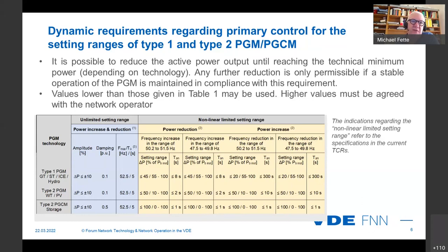Everything is tested in the factory. Everything is tested under the conditions we have to establish at the moment. But we want to know how it works in the future, and whether it works when we lose short circuit ratio, when the grid becomes weaker than today, and we lose inertia, so that the different plants will be operated and support the grid, supporting and forming, with their kinds of technologies. So a lot of discussions, more than one year. This table is only a small extract. We want to set this up for a lot of distinct generators and PGMs so that we can know exactly which kind of technology could support our grid in the future.